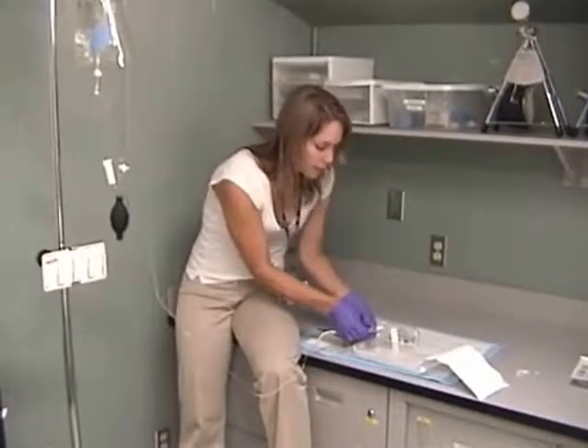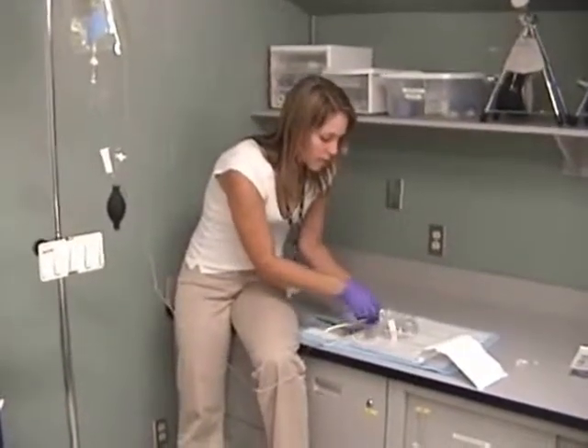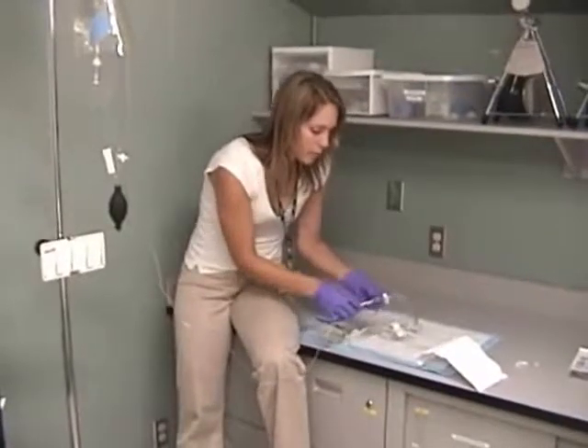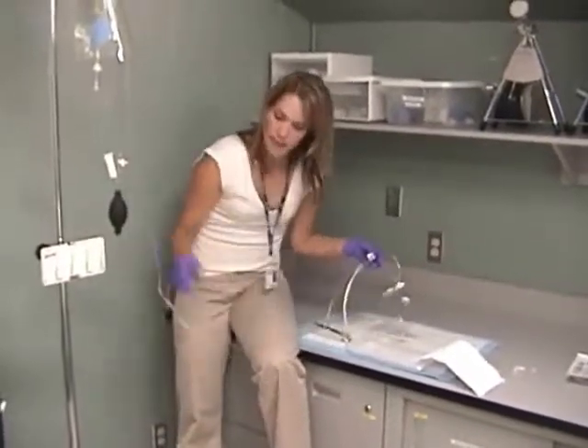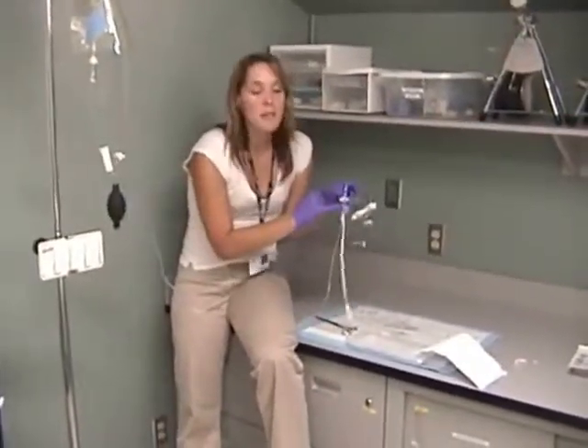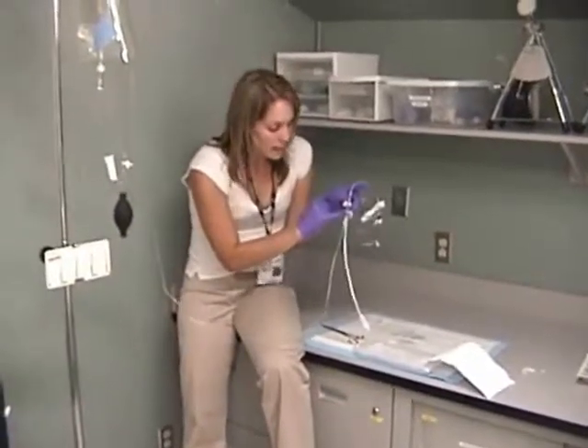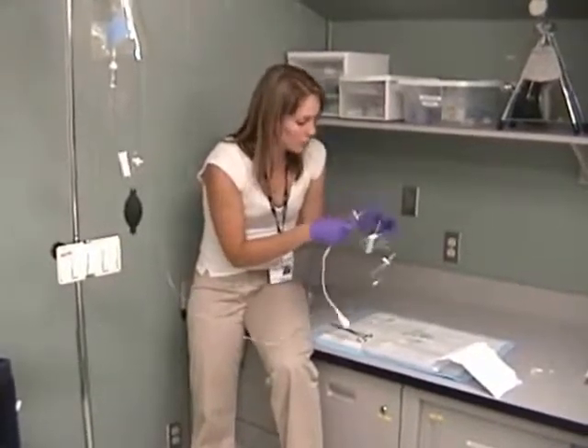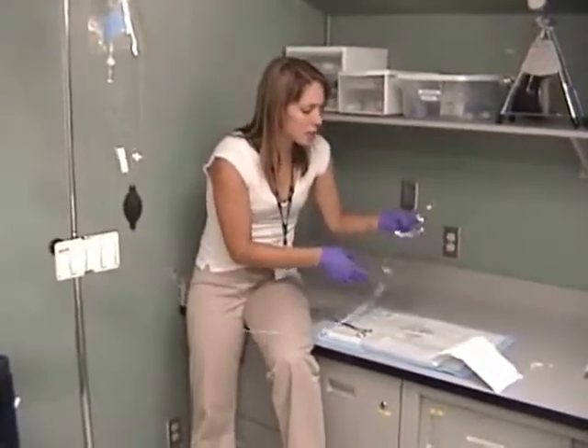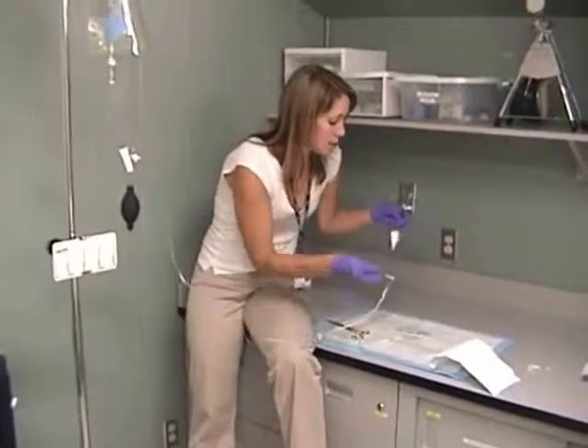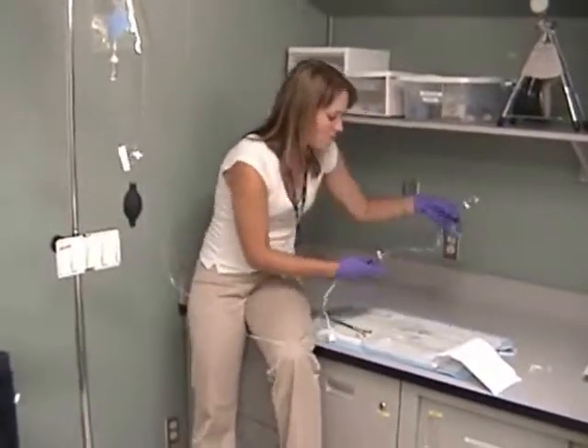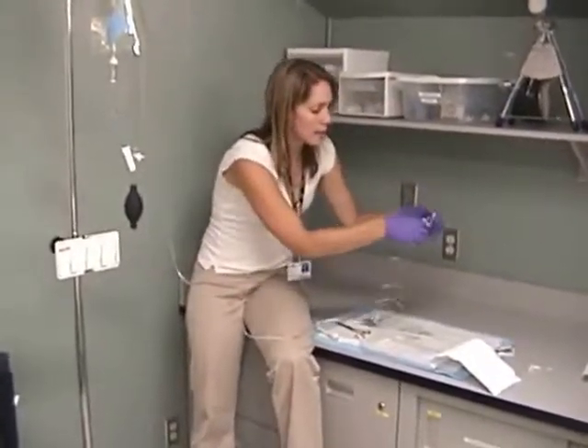Okay, so once you've got all those bubbles out, you can turn that stopcock off to the side port there and double check this section for air bubbles. A common spot for air bubbles to collect is right in the transducer, and they do put a little black marker in there to help you identify if there is a bubble in there. The next piece to flush is this last piece of tubing here. Take off that paper tab and it goes down to the next stopcock.